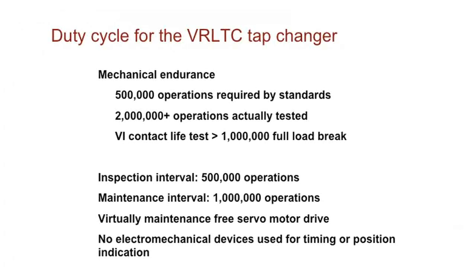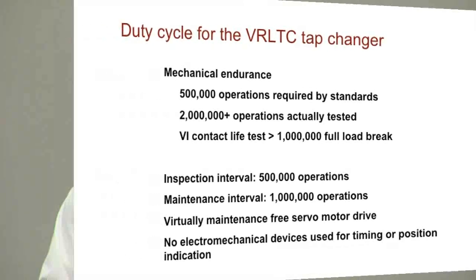Mechanical endurance, 500,000 operations is required by the standards, but we actually tested 2 million operations. And then the contact life test was greater than 1 million on the full load. Inspection intervals, we have 500,000 operations, which is just an inspection interval. Then we have a maintenance interval, which is after 1 million operations, which will take quite a few years. I think I've got a slide here to show the time on that. Virtually, it's maintenance free because it's a servo motor.